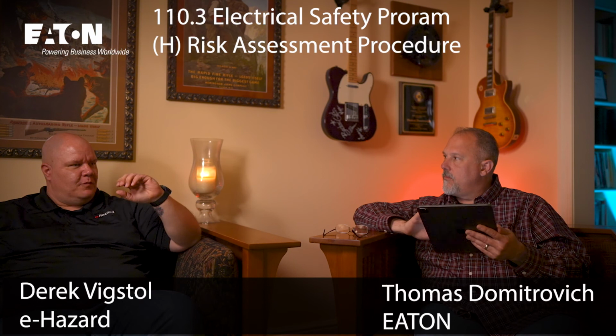All right, I think we're pretty much done with the risk assessment. We know it's a very complicated topic. Once you get the likelihood of occurrence, the potential severity is what's going to help you determine what you're going to do about it, right? So my gloves are going to be based on my voltage. My arc rated PPE is going to be based on incident energy. Or maybe the incident energy is so high that I want to use remote racking or remote switching.